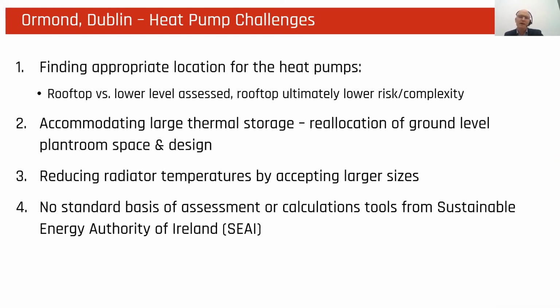We found that we could get eight CAHV units on the roof, and it took up a space of less than 100 square meters, which was important to us, because one of the downsides on the PV, the equivalent PV, was coming out nearly 900 square meters. And on this development, the roof space was important to us, because part of the amenity in the external space was the various terraces. So we didn't want to use PV.